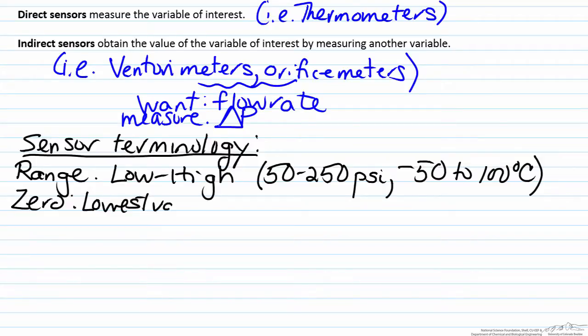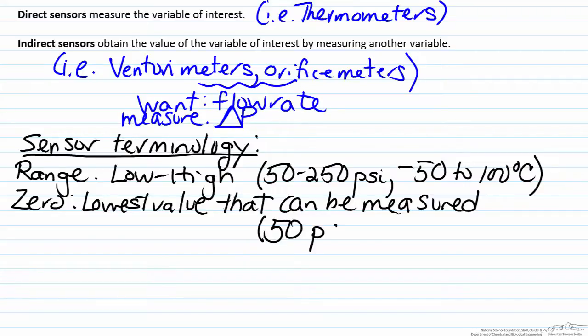Another value of interest is the zero. The zero represents the lowest value that can be measured by the sensor, so in some cases particularly measuring flow the zero will be zero, but in many other situations the zero of the sensor will in fact not be zero. If I look at the two examples that I provided above with the pressure range and the temperature range, the zero is 50 psi for the pressure sensor and negative 50 degrees Celsius for the temperature sensor.